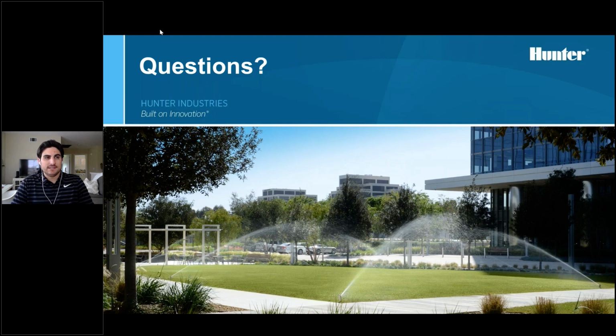The ICD SEN is an awesome piece of hardware we can offer on a traditional 2-wire system to send sensor data up the 2-wire path back to the controller. That's super useful if we have, say, a flow meter that's really far away from the controller. We don't want to hardwire it in, so we can just put a sensor decoder on our 2-wire path, splice our connection that would typically go to a solenoid into your sensor leads, and send flow data up the 2-wire path back to the controller.